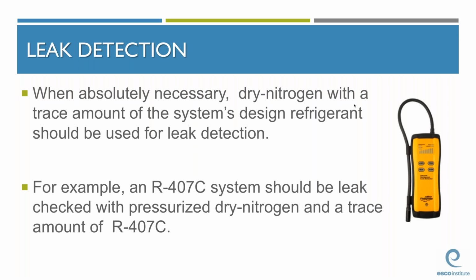There has been some confusion over the years regarding the use of a trace gas. It was thought by many that the only refrigerant that could be used as a trace gas is R22, but that's simply not true. The EPA never specified specific refrigerants that can or cannot be used as a trace.